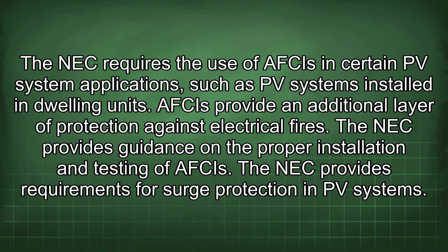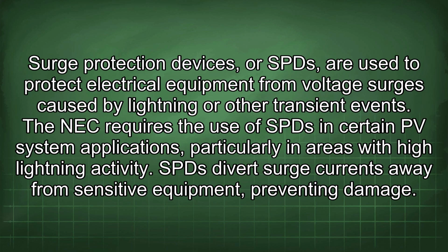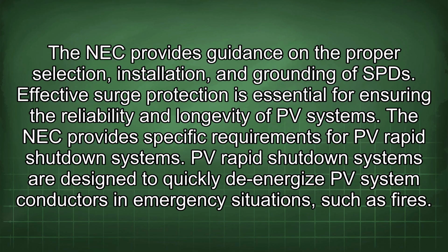The NEC provides requirements for surge protection in PV systems. Surge protection devices, or SPDs, are used to protect electrical equipment from voltage surges caused by lightning or other transient events. The NEC requires the use of SPDs in certain PV system applications, particularly in areas with high lightning activity. SPDs divert surge currents away from sensitive equipment, preventing damage. The NEC provides guidance on the proper selection, installation, and grounding of SPDs. Effective surge protection is essential for ensuring the reliability and longevity of PV systems.